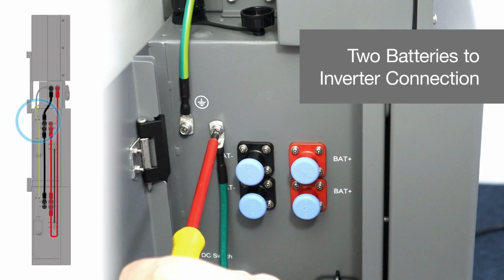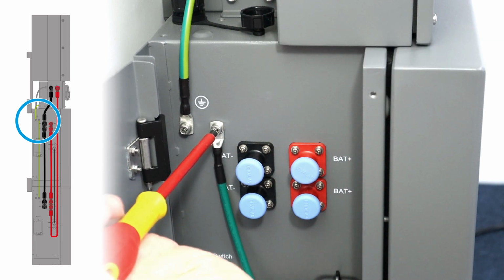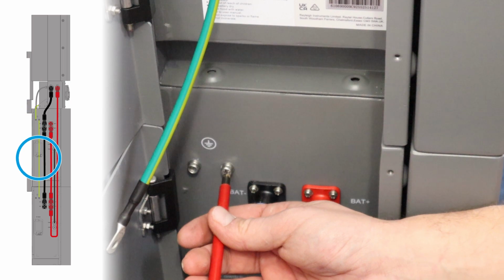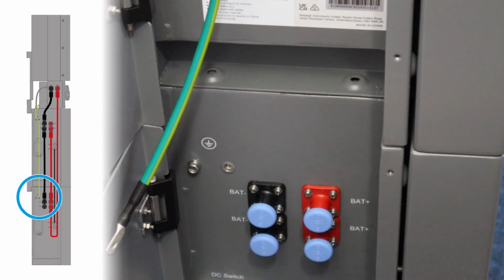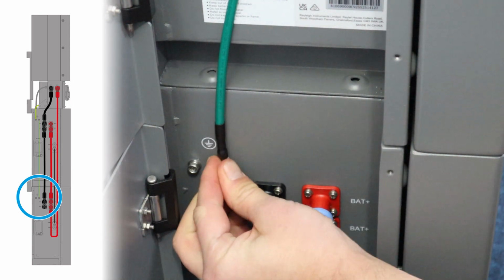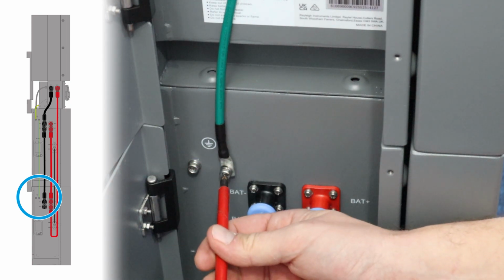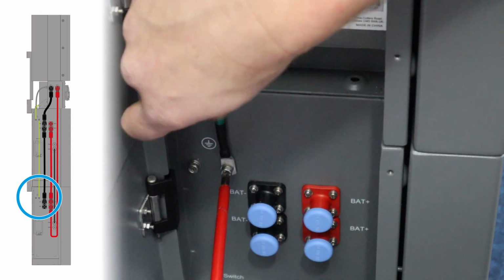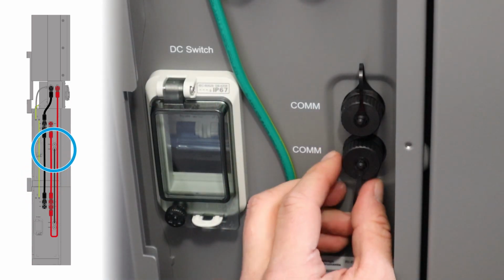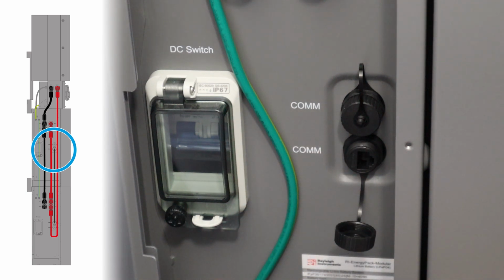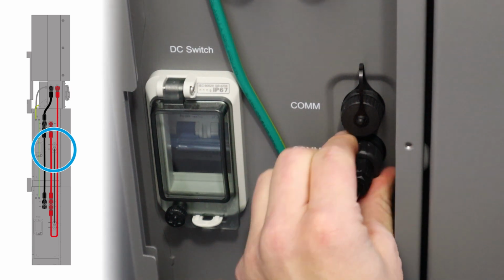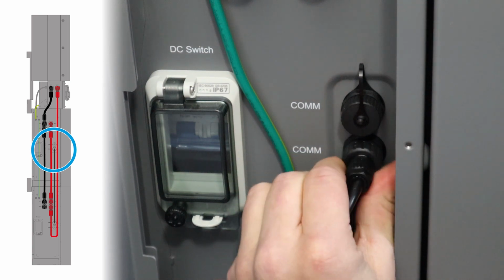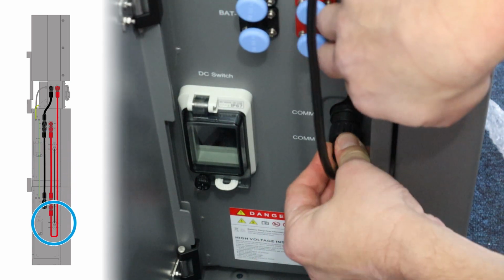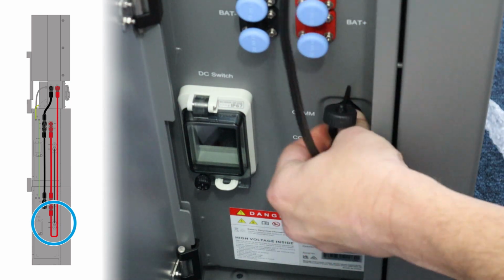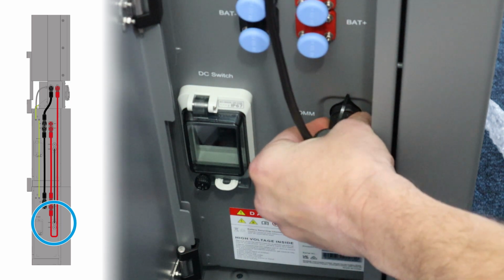For a 2-battery installation, start by installing the earth cable between the spare earth port on battery 1 to one of the earthing points on battery 2. Now unscrew the bottom communication port cover on battery 1 and connect the communication lead. Next, unscrew the top communication port cover on battery 2 and connect the other end of the communication lead. This allows the inverter to see and communicate with battery 2.